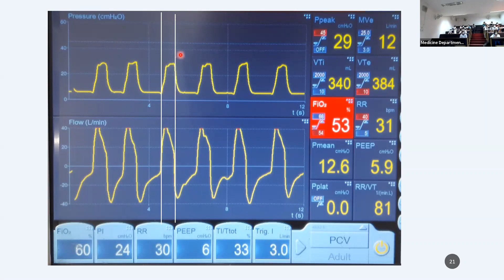In this, a very important thing is we set a TI by T total. Why? Because this PCV mode is time cycled. Time cycled means that at this point of time, inspiration begins, the pressure rises to the PI. As we can see, the flow is positive and the patient takes in a flow. And after a particular inspiratory time we have set, it cycles into expiration. Whether the patient receives adequate volume or not, it doesn't matter. It depends on the PI and the time, how much the patient is getting. Then again, this is the trigger variable, that a particular 3 liter per minute flow is required for the ventilator to assess the breath.